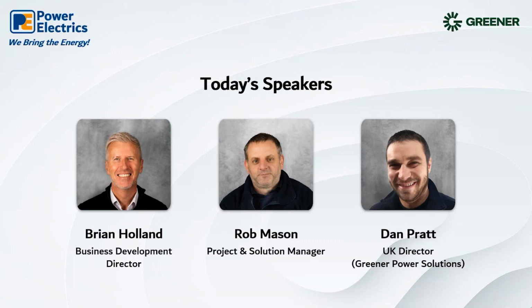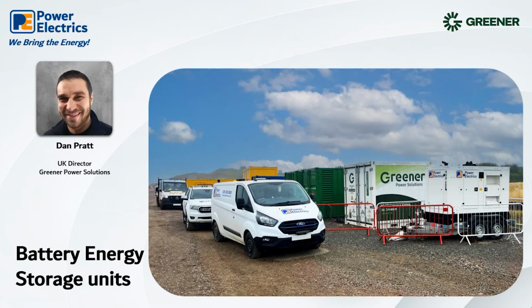Power users are getting quite familiar using smaller lead acid battery systems to hybridize smaller generators up to around 60 kVA. These are great for certain applications, but do have limitations due to the inverter size and the battery chemistry being used. High voltage lithium ion battery systems are much better at reacting quickly and can discharge or take in energy to charge much faster than the lead acid systems. Greener battery systems have a single 250 kilowatt bidirectional inverter, allowing the battery to discharge or charge at the full rate of 250 kilowatts at any time.